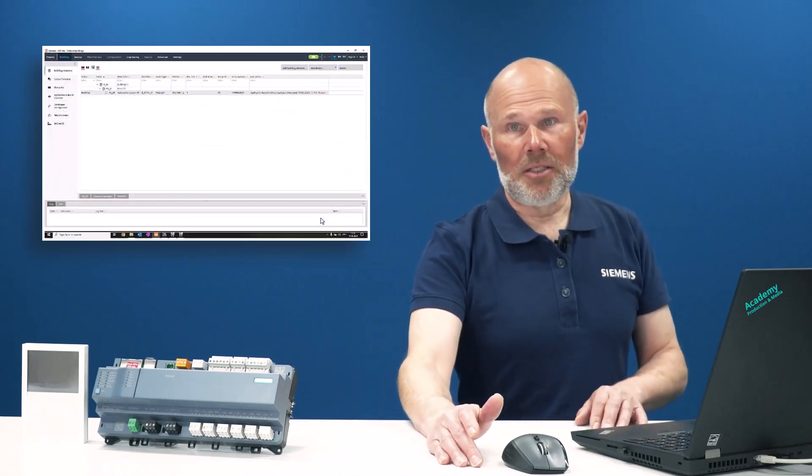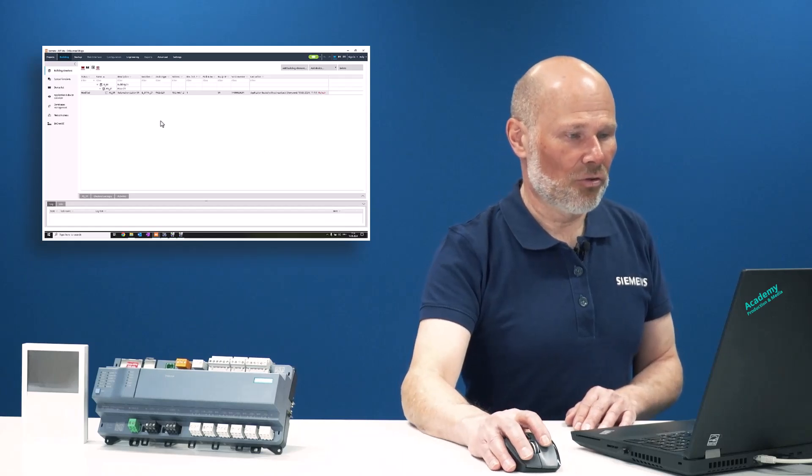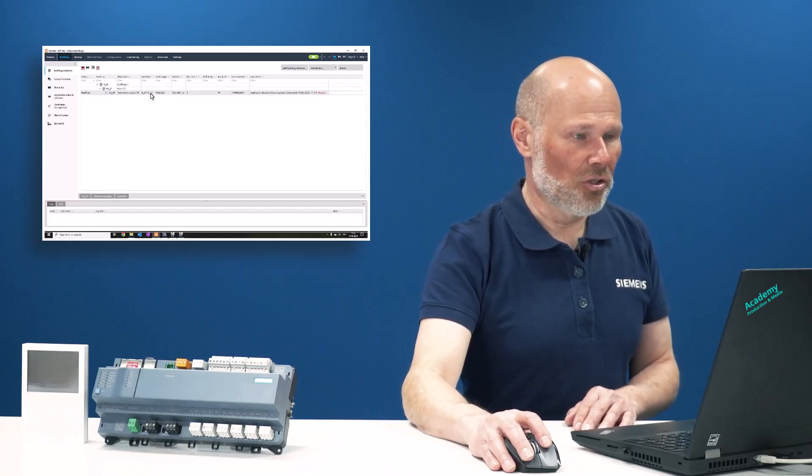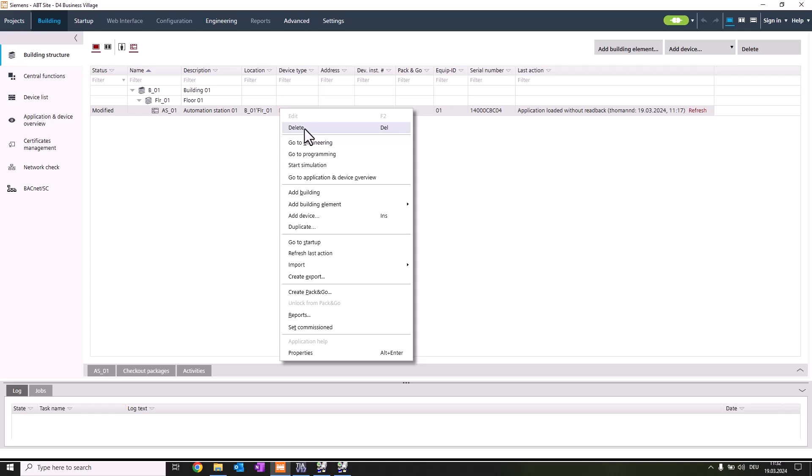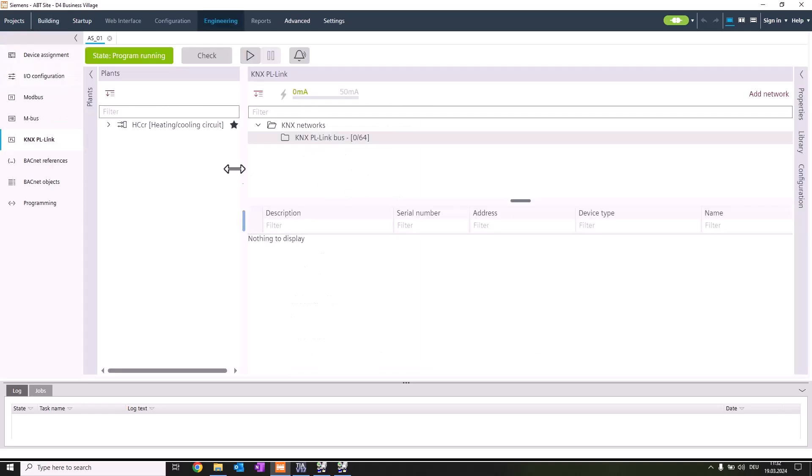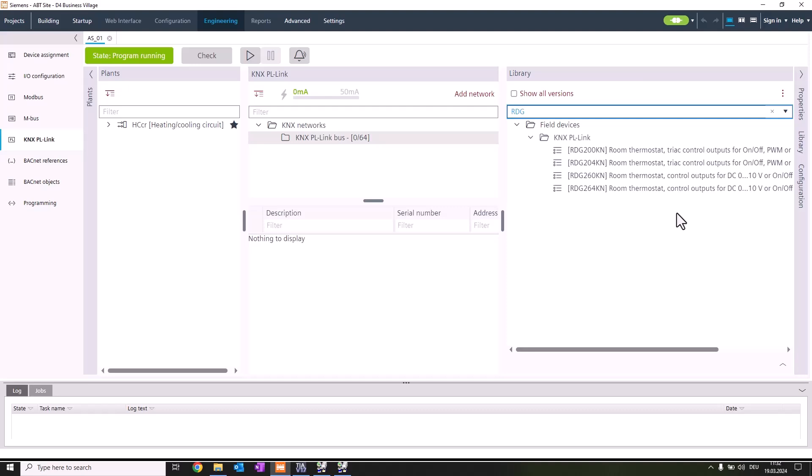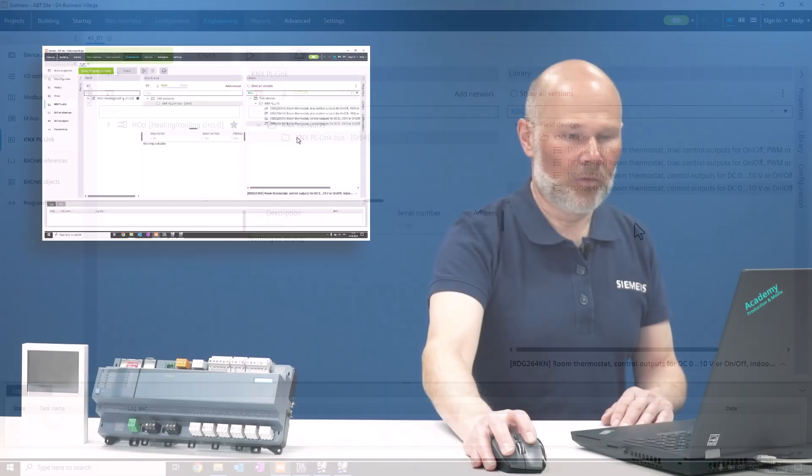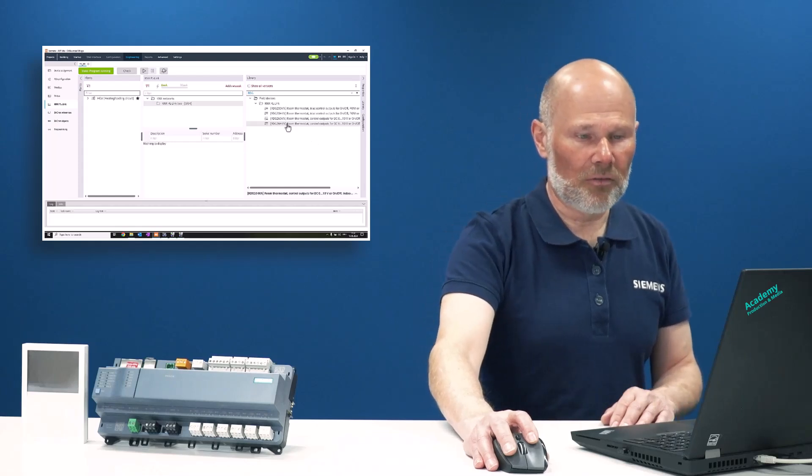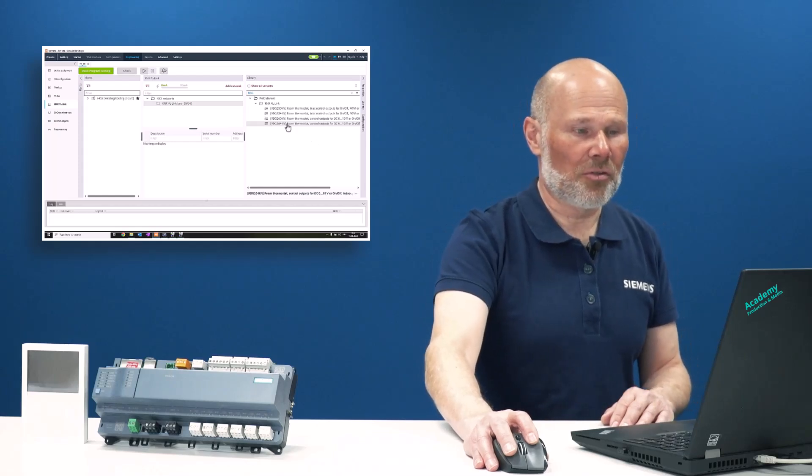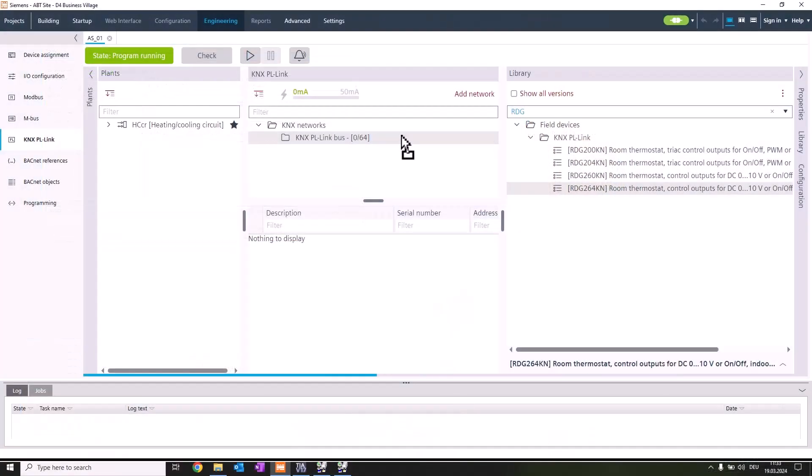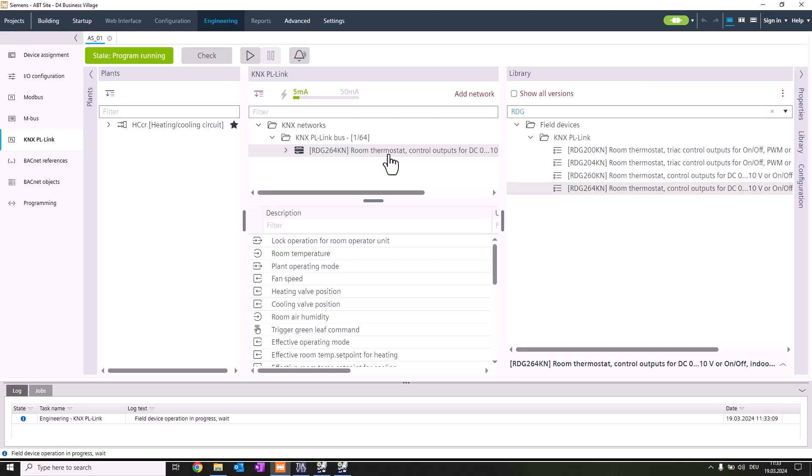The first step in ABT site is we're switching from building structure to the engineering editor and jumping directly to the KNX PL-Link editor. Here we see the KNX PL-Link bus. We're using a simple filtering with RDG to find devices available in the library. We're taking RDG 264 and drag-drop it to the KNX PL-Link bus. This takes a moment and now we're configuring the thermostat.